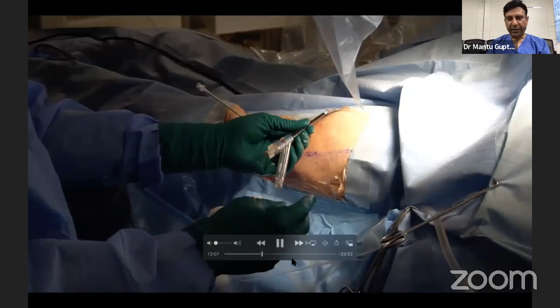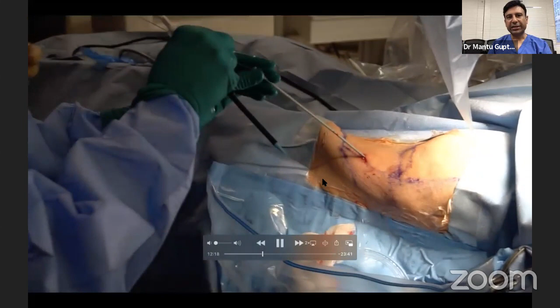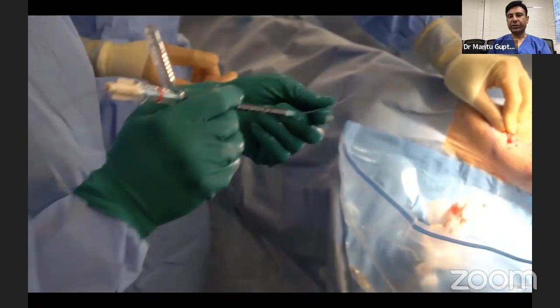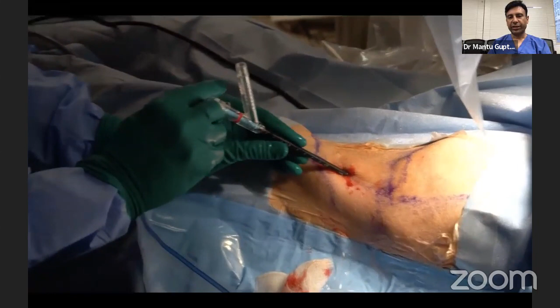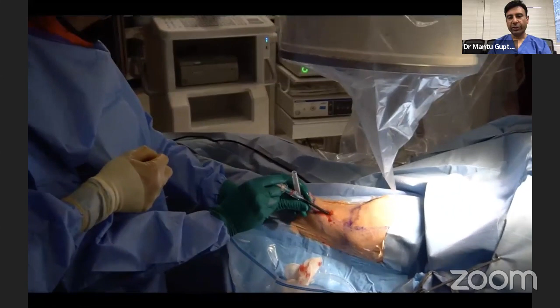This is the ClearPetra sheath. It's a single action, single step dilation, and it's got a side port for suction, so you can suction the particles out. The nice thing is you can bring the particles out to the side port without removing your scope from the sheath. So you can go in and out very quickly compared to a metal set, where you have to come all the way out, let the pieces wash out, and then go back in. So it saves a little bit of time. And there's also continuous suction during the procedure, so the smaller dust particles are coming out as we're doing the procedure.